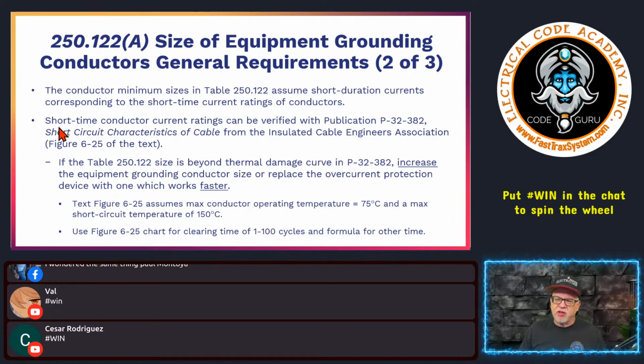All right, it says short time conductor current ratings can be verified with publication P32-382. I don't know if any of you have ever seen that document, had access to that document. We see this stuff all the time. It's in our grounding and bonding course. You'll have a cutaway of it. So if you have our grounding and bonding course, you'll see this figure, this graphic that depicts it. But this is the ICEA that drives that. For you guys, you really don't need to worry about that as long as you follow 250.122.